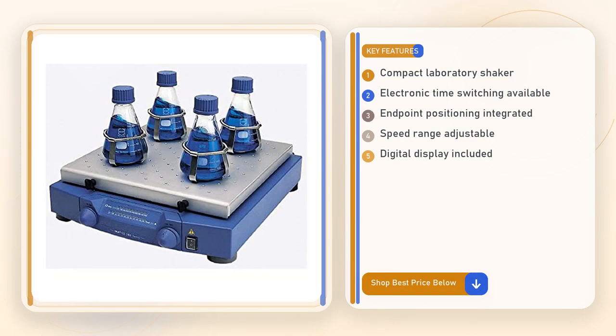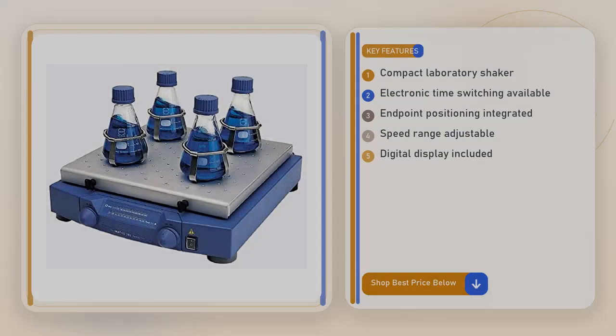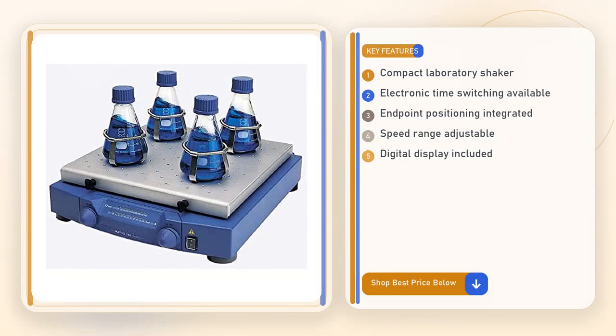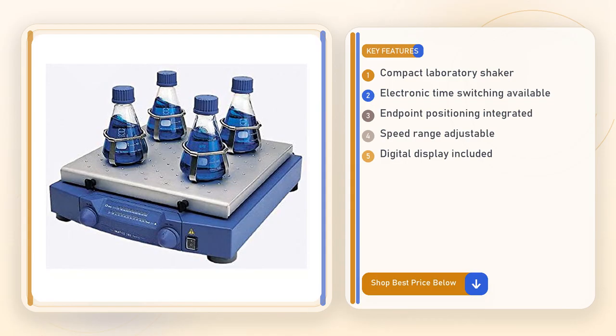other equipment around. Talking about daily usability, the digital display is clear enough that you can glance at it and see the current speed, remaining time, and which step you're on. The interface isn't a touch screen, so you won't accidentally change a setting with a stray finger, but the buttons are tactile and give a satisfying click. In my own experience with a similar IKA model, I found that the clock's accuracy stays within a few seconds over a full 8-hour run, which is more than adequate for most protocols that don't demand millisecond precision. The speed range is wide enough to cover low rocking to high orbital shaking, so you won't feel limited when you switch from a gentle cell culture agitation to a vigorous nanoparticle dispersion.